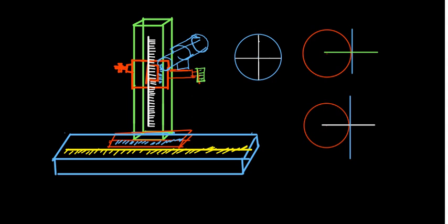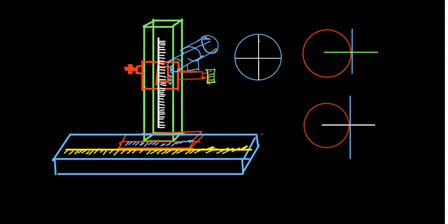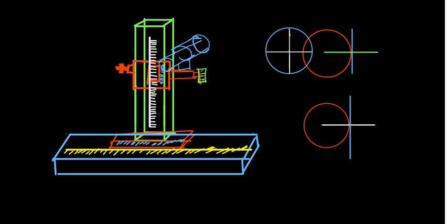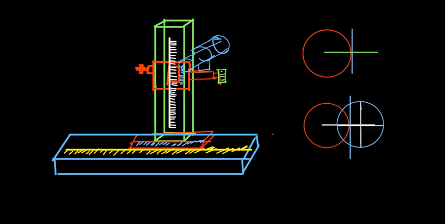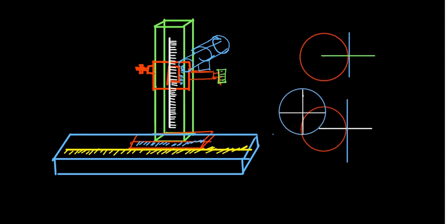So you can make this type of lateral motion, and once you move it, have a good look at it when you move it like this. So your crosswire, there is a crosswire. Using this crosswire you can aim it, so you can just simply hold it in this position and take down that reading. Again, just move this one to here, and it appears to be moving to the other side. So you can hold it to this side and get the other reading, and I accidentally marked all that here. It should be this side, and you just get the difference.